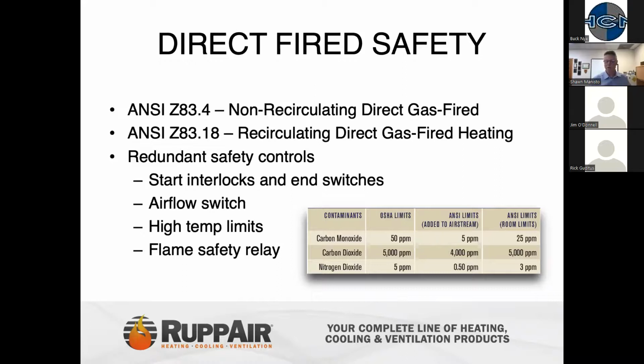And the direct fired, let me just clarify, the direct fired units add a minimal amount of moisture to the space. It's also been a misnomer as far as direct fired units creating a lot of moisture to the space. Obviously, part of combustion is H2O or water. But again, they actually work as a humidification system, if anything else, in the cold of winter, providing some level of humidification to the space.